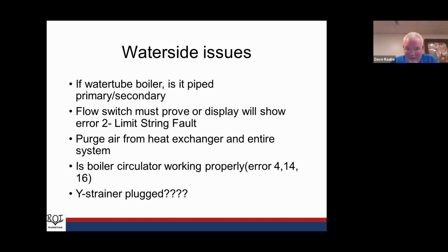The last thing, and this goes back to that flow switch: if the flow switch won't make, is there a Y strainer in the system? And if so, is it plugged? The problem with Y strainers, we recommend them, and we recommend you use a larger mesh in there. We really want to keep the bigger debris from getting back into our heat exchanger. Y strainers are an item that requires maintenance. You need to pull the screen out and clean that periodically.